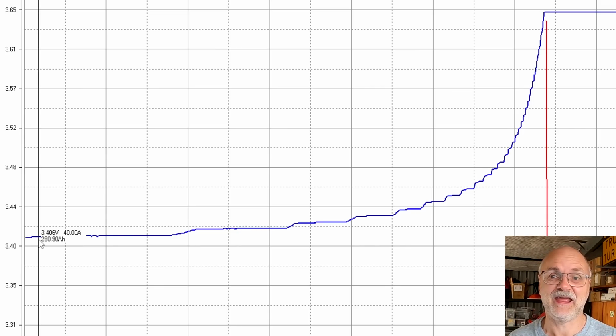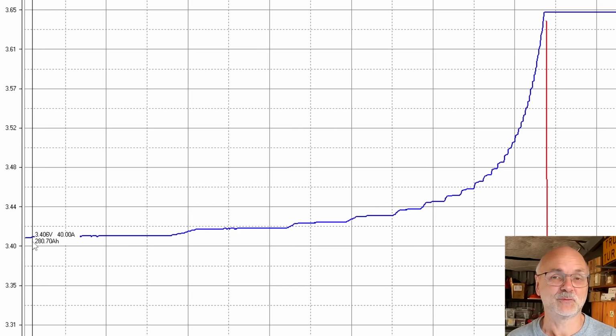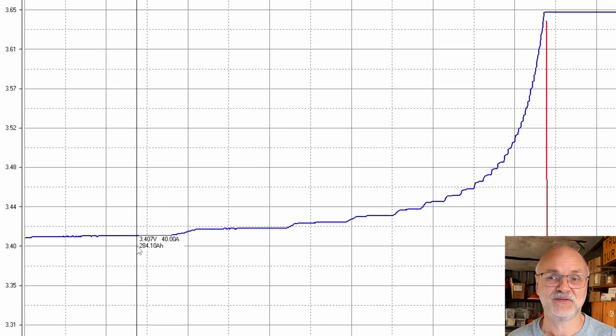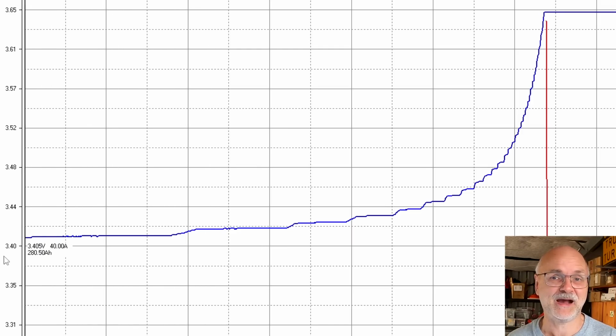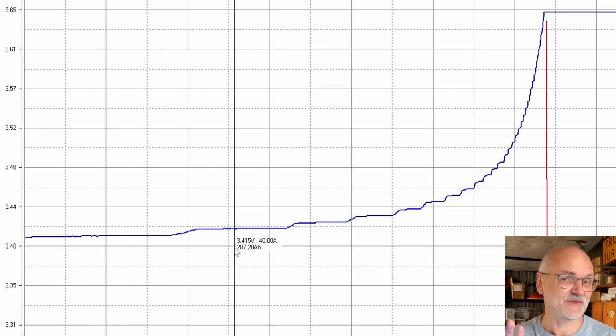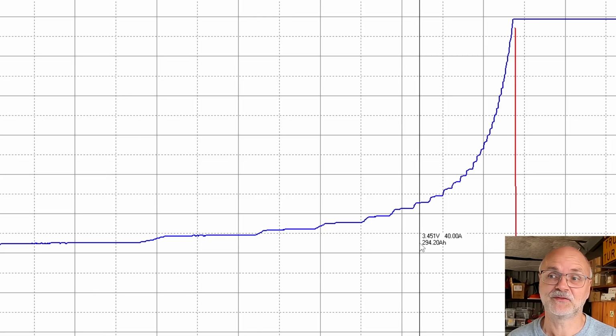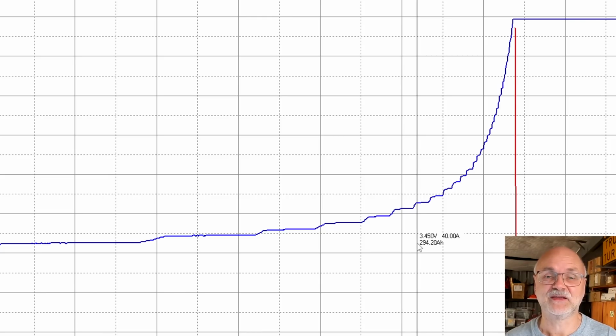If you have a sunny day, you can easily exceed 3.4 volt charge voltage for quite a while, and the balancer would kick in already, balancing in this still flat part of the curve, which causes imbalance. So from our testing on the channel, 3.45 is the magic number where you want to start balancing.